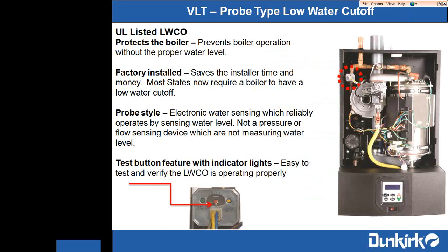Some other nice, unique features about the boiler. There is a factory-installed UL-listed low water cutoff with a test button. More and more municipalities are requiring low water cutoff. Some other of our competitors in the modulating arena require the contractor to purchase a low water cutoff. Here it's installed, and that's about another $150 to $200 savings for the contractor. This low water cutoff also happens to have a test button on it. So if the inspector requires that the contractor prove that the low water cutoff works, they don't have to disconnect anything. They simply press the button.